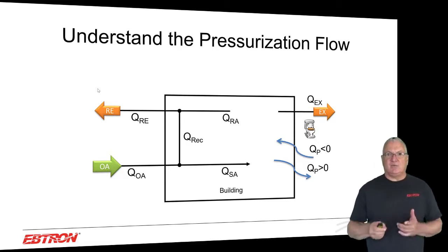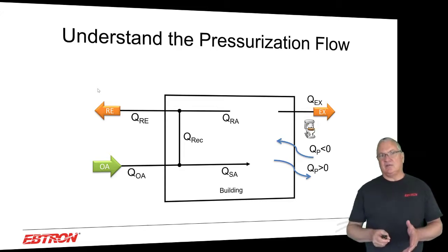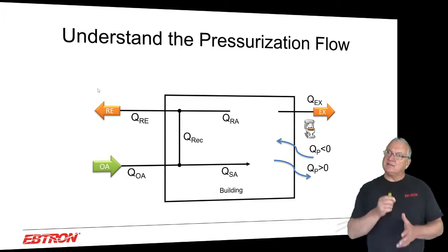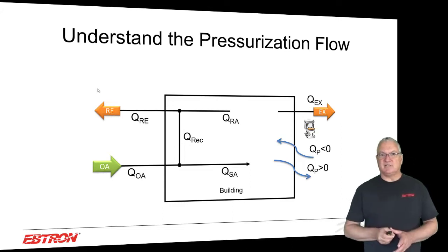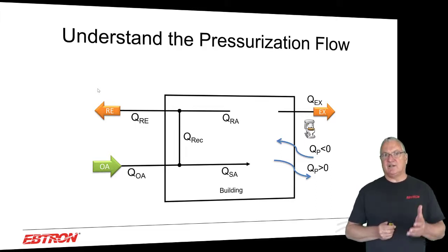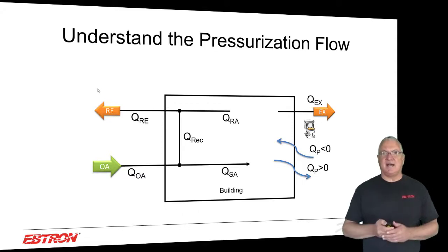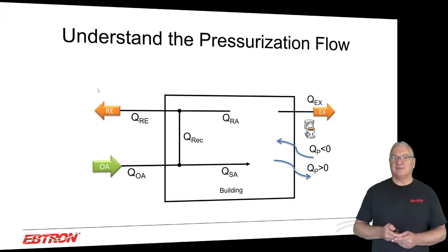And there's two reasons I want to point this out. One, I want you to understand that when we talk about doing this, these other options are typically better places to measure for more accurate flows. But also to let you know that if you aren't understanding that this affects building pressurization, anything you do that affects supply-return airflow differentials is going to affect the pressurization of the building. And so if you do sloppy fan tracking or ride fan curves and things like that, you have a potential for some real building pressure problems.